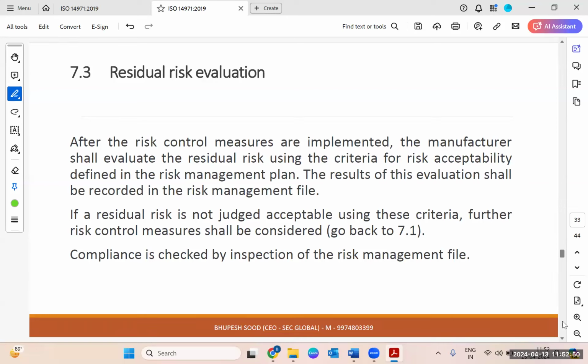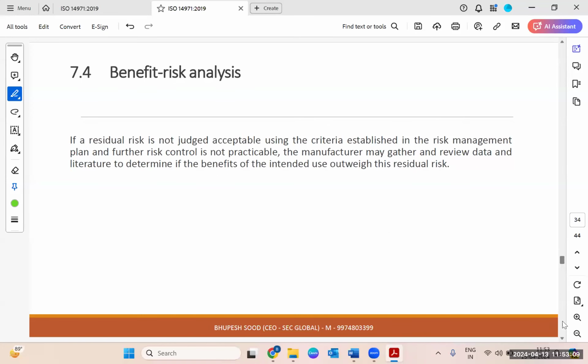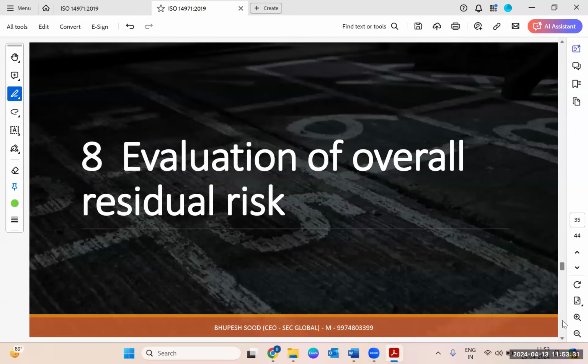When we say that there is a residual risk, we have to make sure that residual risks are identified, and the patients are made aware of the residual risk so that they can take appropriate measures. And as a management, you have to decide whether to release the product as a medical device or to keep working on it. In the risk management file, as I told you, in the end we write the benefit risk analysis. The benefit risk analysis is an input to the person releasing the product, on whether they should release or not if there are issues. Then we have the evaluation of the overall residual risk, which means that if any residual risk still remains, we do a residual risk analysis.